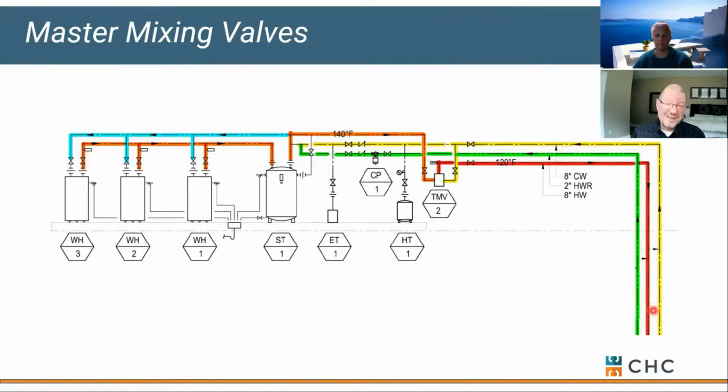What's the fix? If you know tempering valves, this should be really obvious. Our recirc pump is only tied into the hot water side of our tempering valve. It only gives us access to the orange side of the valve. We have no flow through this yellow line. So if this port is closed, we are basically deadheading our circ pump. And if we deadhead our circ pump, then this line really gives off temperature and cools down.